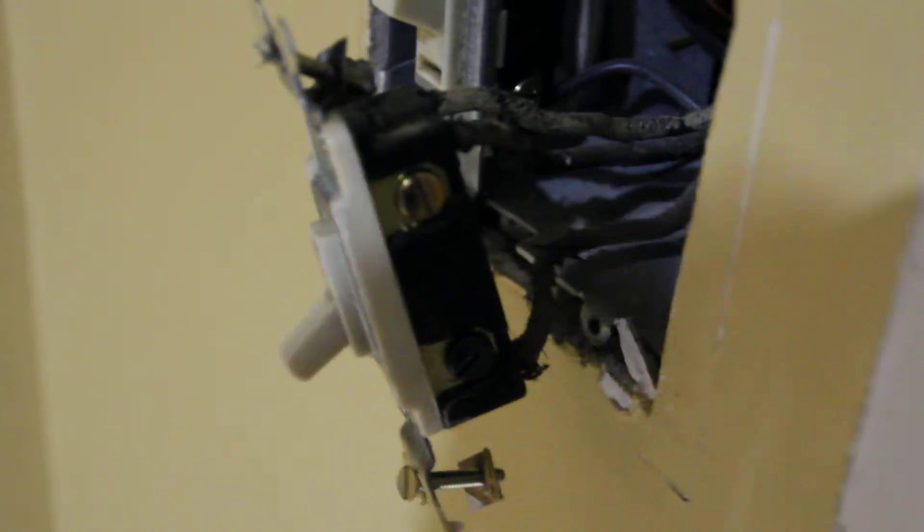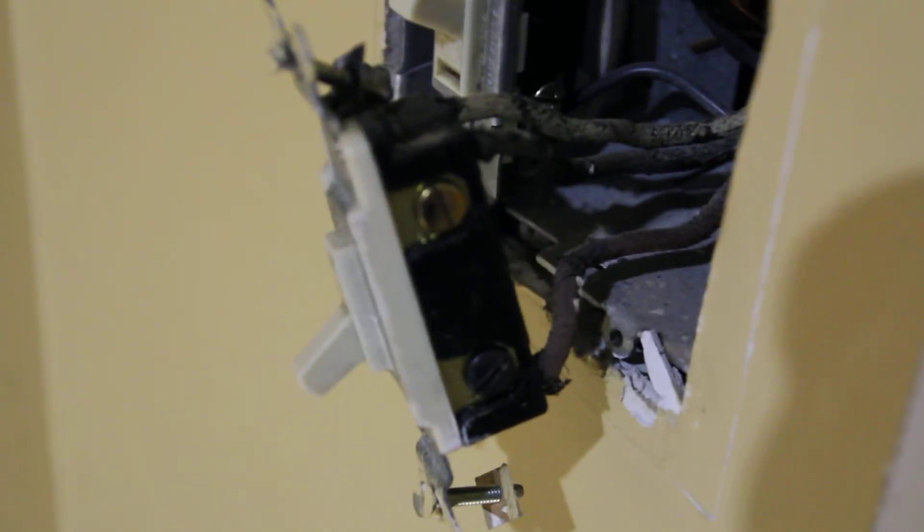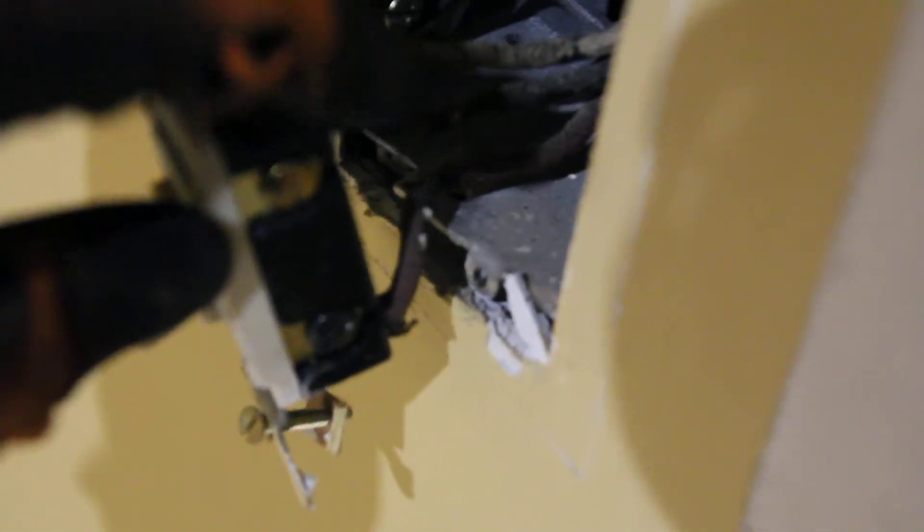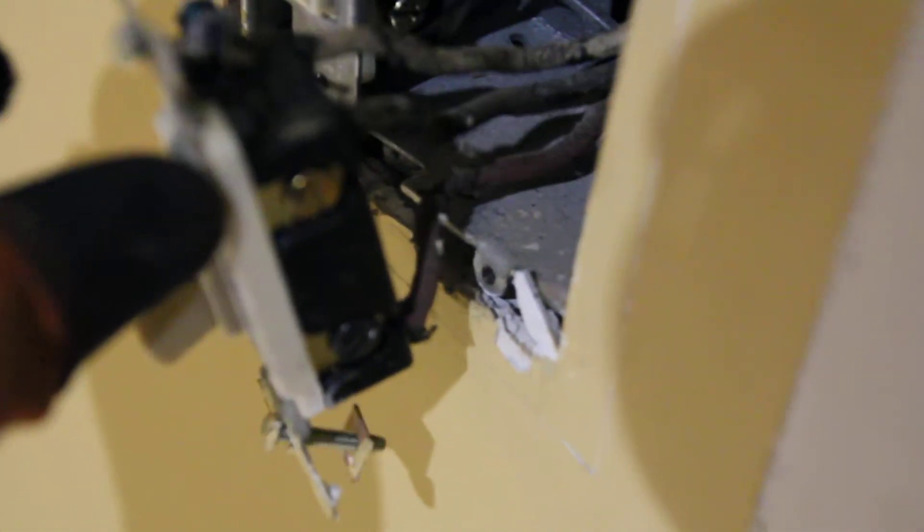It's one three-wire that's all that's in here, so the light wire does not come in. So what they've done is they've taken the white wire and they've made that one of the traveler wires. This should be red.